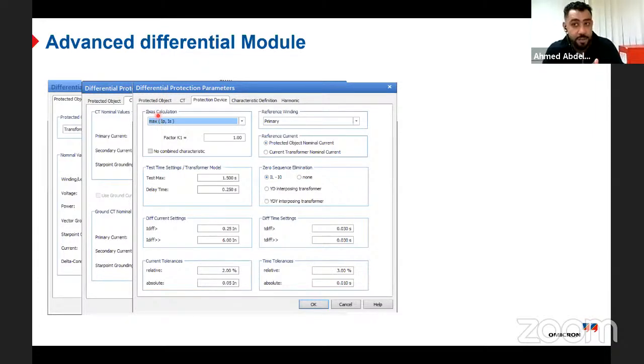You can see in our test universe, we didn't talk about the differential calculation because we said all of them are similar, but the bias calculation depends on the relay itself. So here I choose the maximum of I primary and I secondary because I got it from the relay manual that the bias current is the maximum of IP and IS. Then in Siemens, by the way, you can go here to the bias equation in the drop down menu. You can define exactly the bias equation. We have two generations from Siemens relay. We have Siprotec 4 and Siprotec 5.